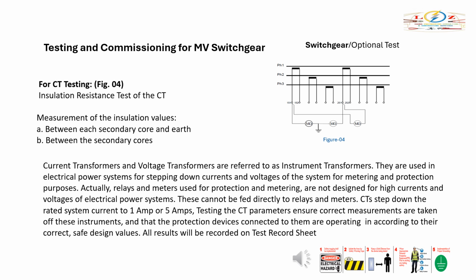Current transformers and voltage transformers are referred to as instrument transformers. They are used in electrical power systems for stepping down currents and voltages of the system for metering and protection purposes. Actually, relays and meters used for protection and metering are not designed for high currents and voltages of electrical power systems. These cannot be fed directly to relays and meters. CTs step down the rated system current to 1 amp or 5 amps. Testing the CT parameters ensures correct measurements are taken off these instruments, and that the protection devices connected to them are operating according to their correct, safe design values. All results will be recorded on the test record sheet.